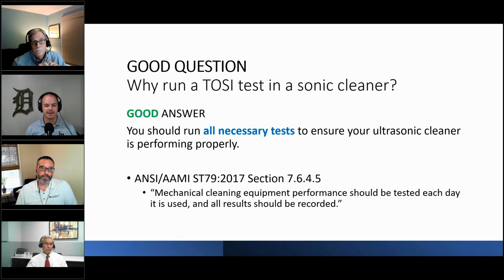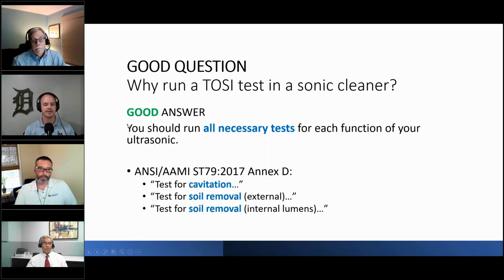So what I believe a better answer to this question would be is that we need to run all necessary tests to ensure that the ultrasonic cleaner is performing properly. And we'll see in ANSI AAMI ST79 that it states mechanical cleaning equipment performance should be tested each day it is used and all results should be recorded. Another quote that's not on the slide here says specifically to test for cavitation each day. That's also in ST79. And for the nurses and scrub techs out there, that same verbiage is also in the AORN guidelines. But let's talk about more support for running these performance tests when we look at the next slide here.